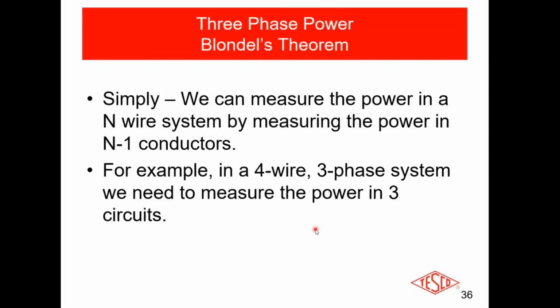How many wires are typically coming into the home? It's a 240 volt service with a 3 wire system. 3 minus 1 is 2. But in the 2S meter, we only got 1 watt meter, which means a 2S meter is not a Blondel compliant meter. What does that mean? That means it is not accurate at times. In fact, I would say it's not accurate most of the time now. How serious is that? We'll talk about that in just a few minutes.